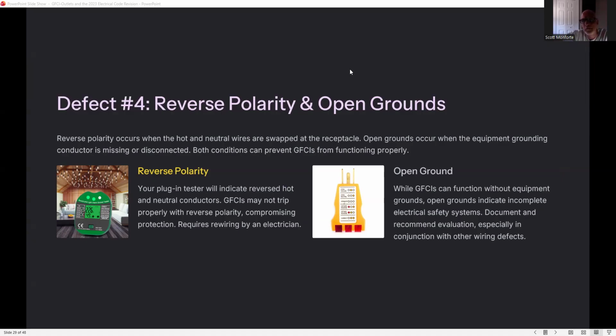So I run into this when you do bathrooms. Your tester says it's non-grounded, but it's a GFCI. Your tester will not trip it. You're going to have to push the button. Then what do you tell the client? You tell the client that the outlet's not grounded, but you are protected from electrical shock, but it's not complete electrical safety. So you probably want an electrician to look at it, but in the meantime, it's not what I would call an emergency or a deal breaker or anything like that. The outlet is protected, but it's not properly grounded. You can't properly test it with a tester.